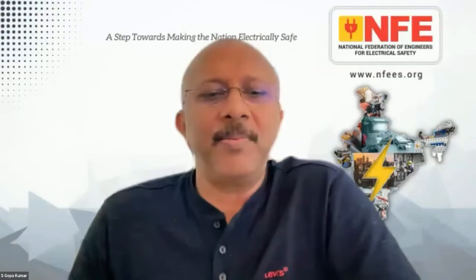No, yes, Krish. So I think it's just to reinforce the equipotential zone and make sure we're staying within that 50 volt touch limit. Like Paul said, it's only if it creates an even more low impedance path. But generally, I see that happening. So the point is the equipotential bonding creates the equipotential zone, and it has to go back to the source, which is the transformer, and that's what the protective earthing is for.